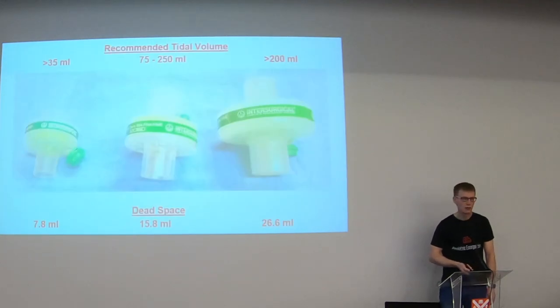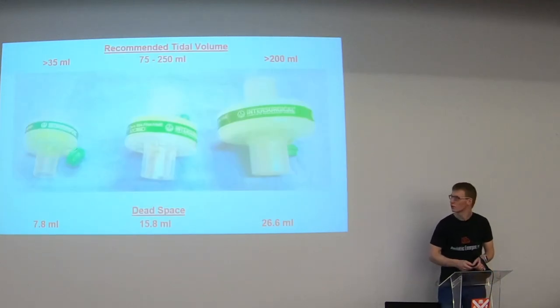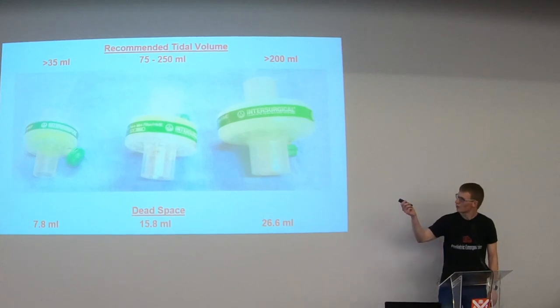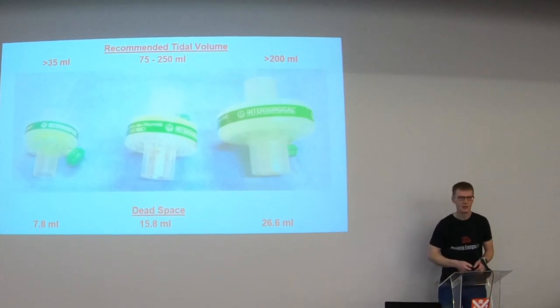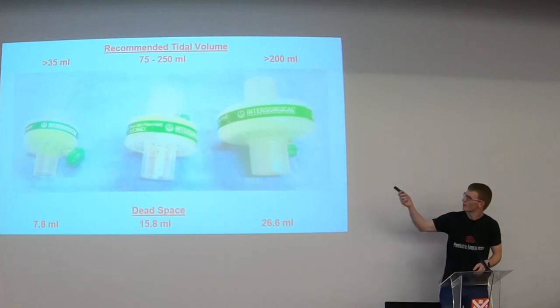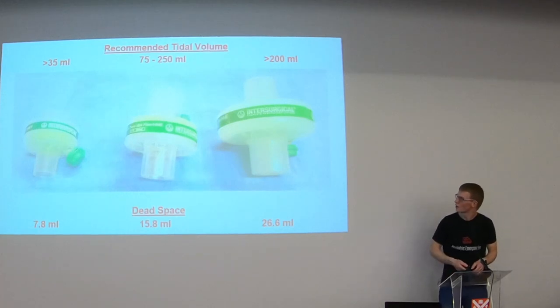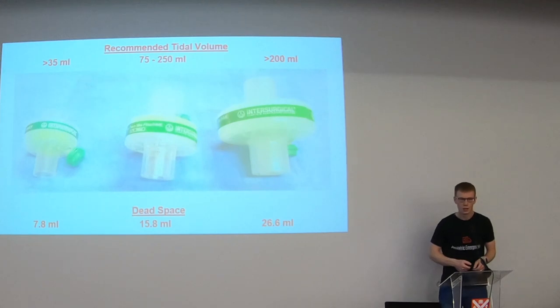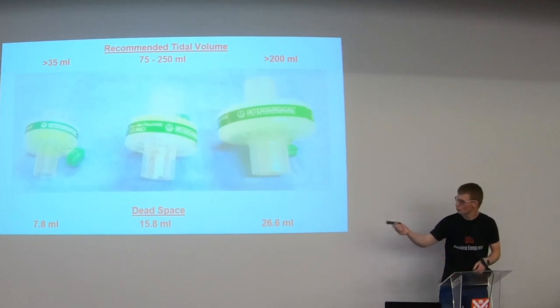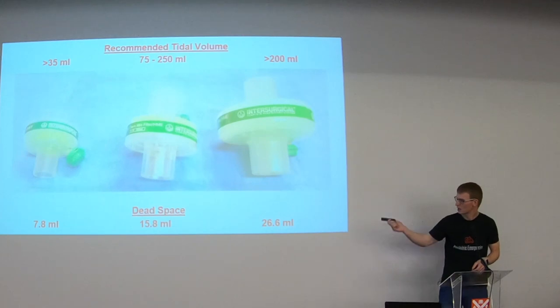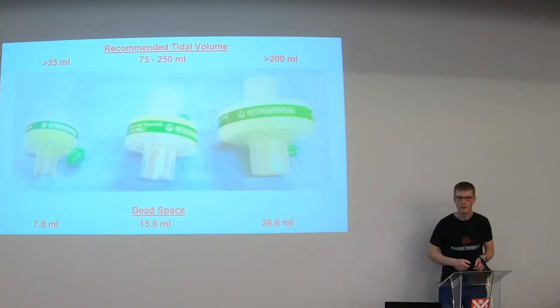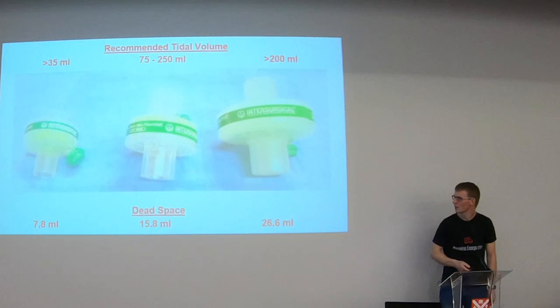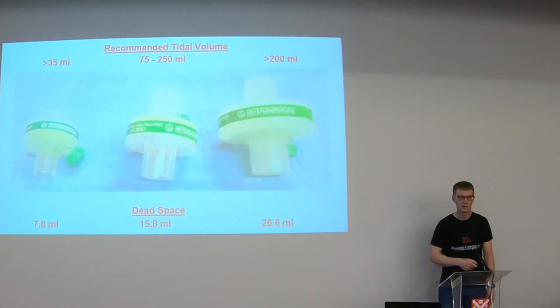And then make sure you're using the right size of filter for your patient. A lot of the manufacturers will say on the filters themselves what the recommended tidal volumes are. So you can see the recommended tidal volumes for each of these particular ones at the top and then the dead spaces down the bottom. So if you had an infant who should have a filter with a dead space of about eight mils and actually put the adult one in with a dead space of almost 27 mils you would expect them not to ventilate particularly well. It surprises you just how much dead space is in one of these things.